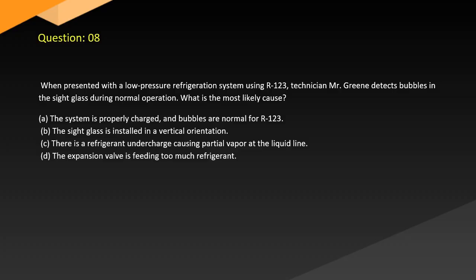Question 8. When presented with a low-pressure refrigeration system using R123, a technician detects bubbles in the sight glass during normal operation. What is the most likely cause? A. The system is properly charged and bubbles are normal for R123. B. The sight glass is installed in a vertical orientation. C. There is a refrigerant undercharge causing partial vapor at the liquid line. D. The expansion valve is feeding too much refrigerant.